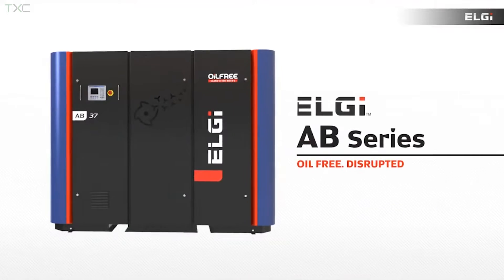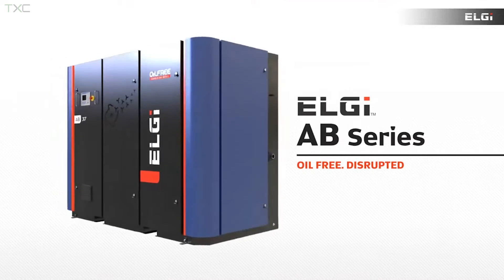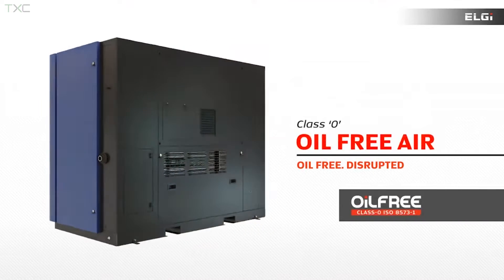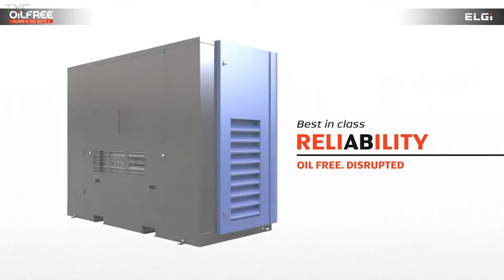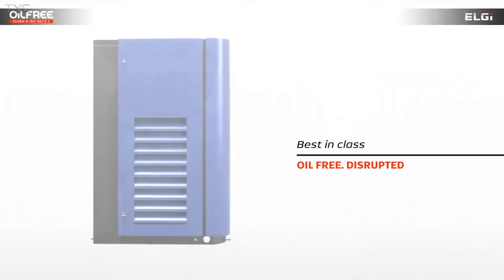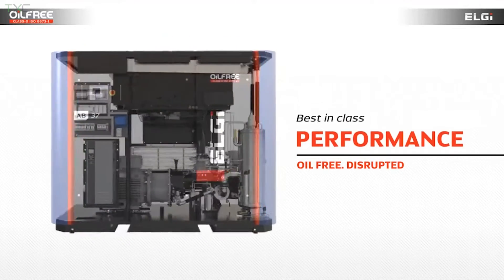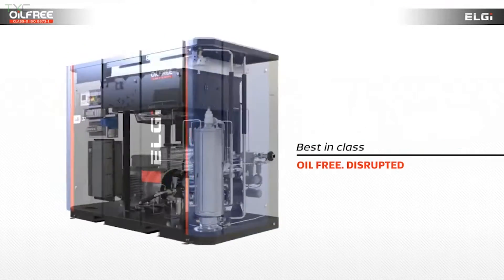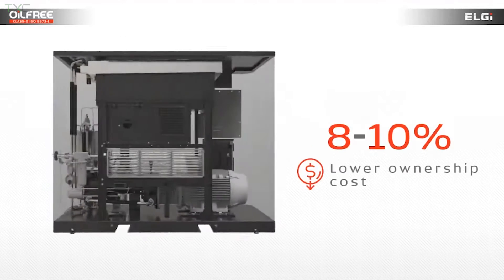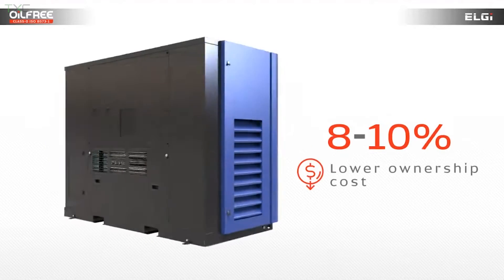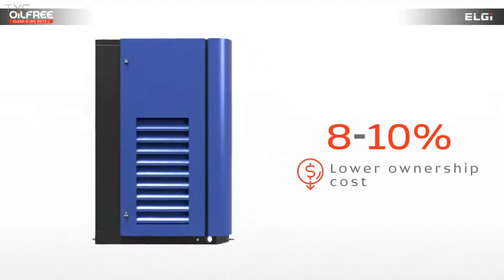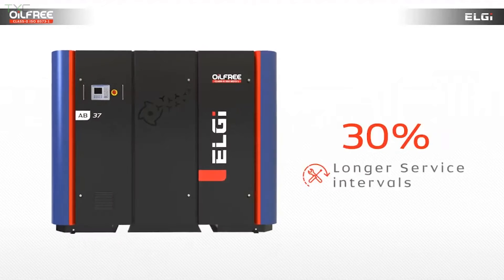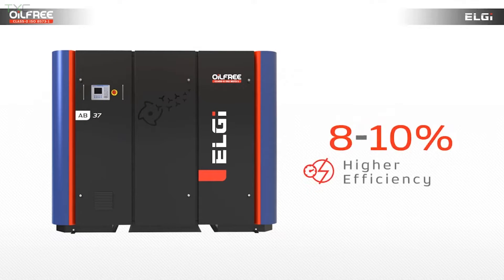Another thing that most customers are not aware of is that even if you choose an oil-free compressor, you still need to have some sort of cleanup filter on the outside of that compressor. And the reason is because just in the air that we're breathing, there are hydrocarbons in the air in very minute forms. So when you compress it, all of that turns to oil. You still need to get it out.